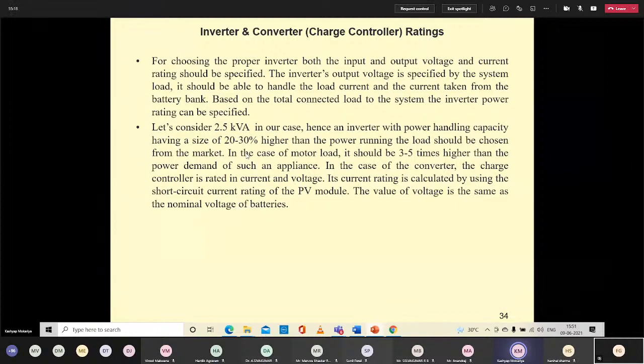In case your machine load is there, then you have to consider 3 to 5 times higher than the power demand. In case your EV charging load is there, you have to consider the initial charging current and the nominal charging current both. In case of an EV charging station, you are designing for the inverter capacity.